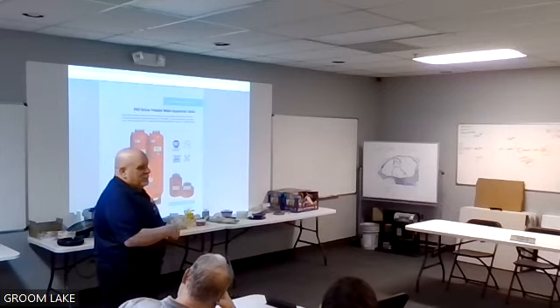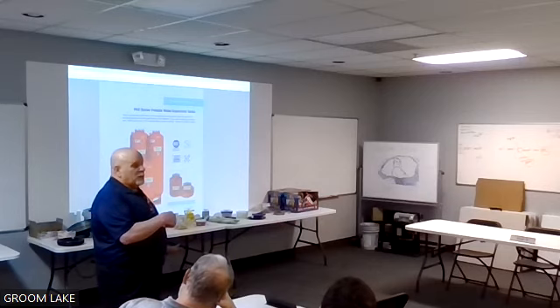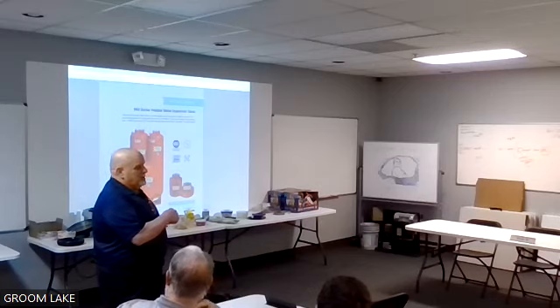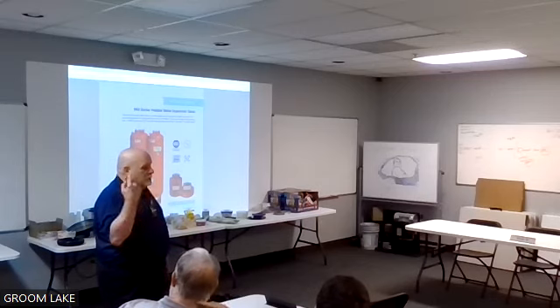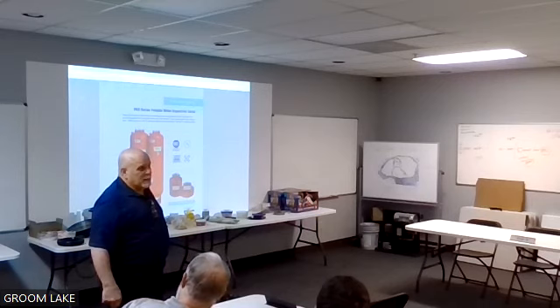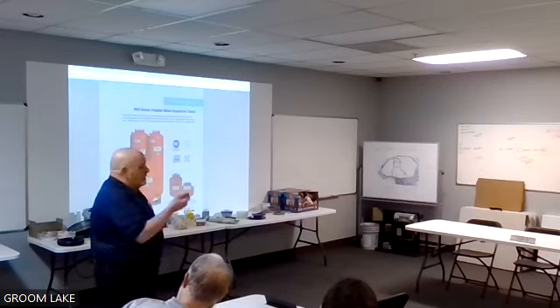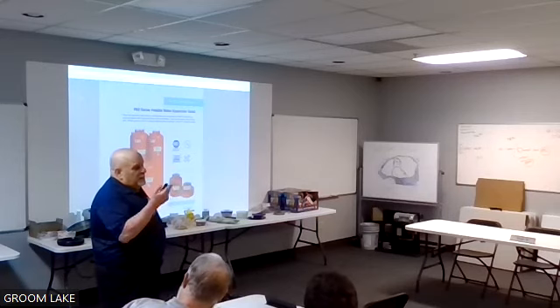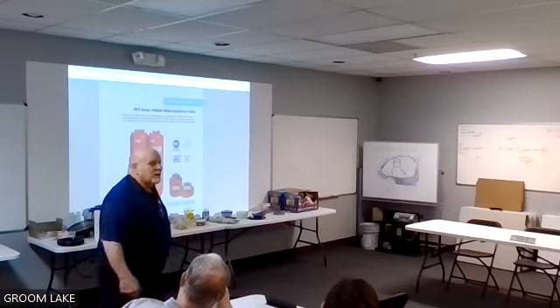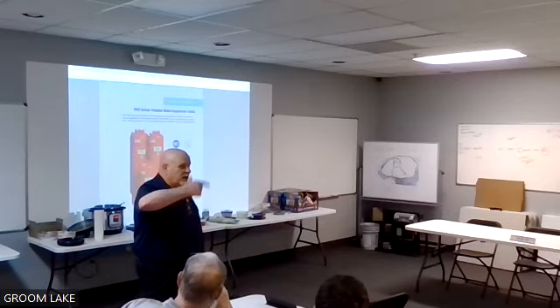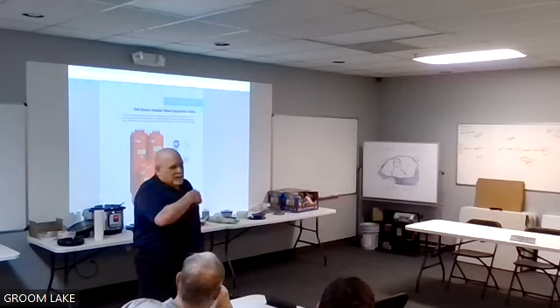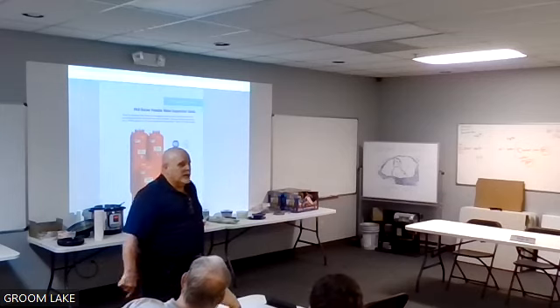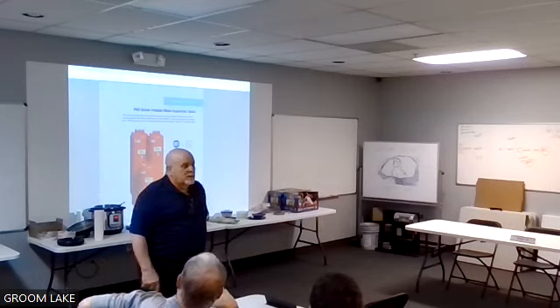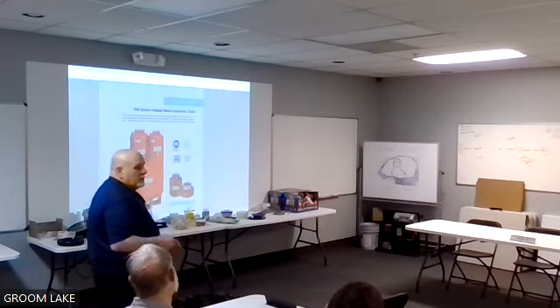And again, you would size these the same way, except I'm going to have 40 PSI of inlet water typically. Whatever the building makeup water pressure is from the boosters, that's what you want to size to. So we always use 40 PSI, go to 145, because all the water systems have 150 pound reliefs. And you put in your volume just the same way, except as you designed it for 145, or 40 to 140, 40 to 120, whatever your system is. And your relief valve would be 40 PSI to 120 or 145 to this 150 pound. And it'll make this PAX selection for you.